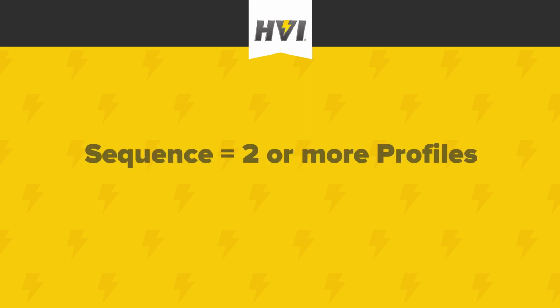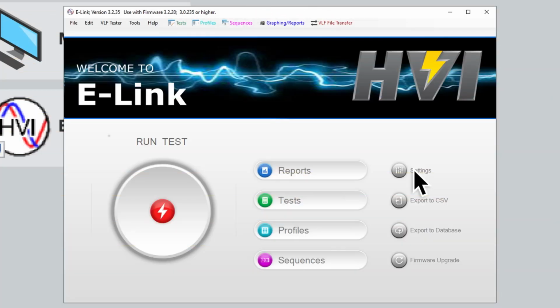Finally, a sequence consists of multiple test profiles that are arranged in a particular order. This is helpful where multiple testing standards need to be run on a single cable, or when cable testing requires more than 5 voltage steps. Let's go ahead and set up a sample profile and then a sequence.